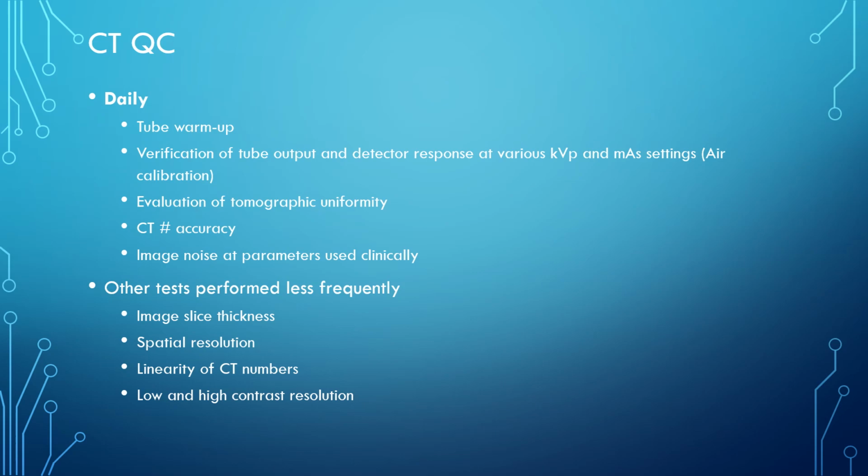the X-ray tube. So if the tube is not adequately warmed up, you cannot have enough thermionic emission of electrons. Therefore, the electrons will not be the correct KVP or MAS, and you won't get good quality images, and you'll get artifacts and things like that in it. So you don't want to use it when the tube is not fully warmed up.